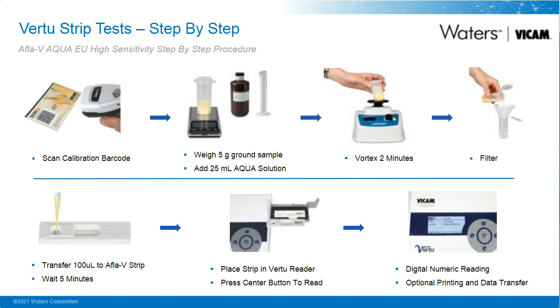What if you want to test more than one mycotoxin at a time on a single sample? Or what if you routinely want to test 1 or 2 toxins and once in a while you'd like to do a deeper dive into your raw material stream and test up to 6 different mycotoxins? You can use the same extraction process that we looked at in our previous slide and just apply 100 microliters of that filtered extract onto each of the strips for the toxins that you're interested in quantifying. The one exception is for vomitoxin testing, you would incorporate an incubator for a brief portion of that method to make sure we have temperature stability during the analysis.